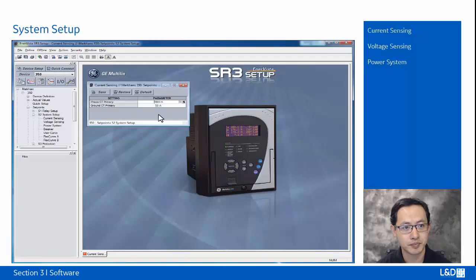And there's a limit, the maximum is 6,000. So if you enter a number higher than that limit, you get a message, and it just limits it to 6,000 amps. And the last way is to directly highlight this number and type in the new setting from the keypad, press the tab key and click the save button, so the new setting is saved into the relay. If the relay has the order code of universal CT, then secondary current 1 amp or 5 amp can also be selected from the software.